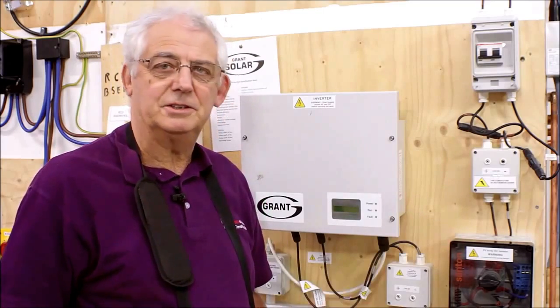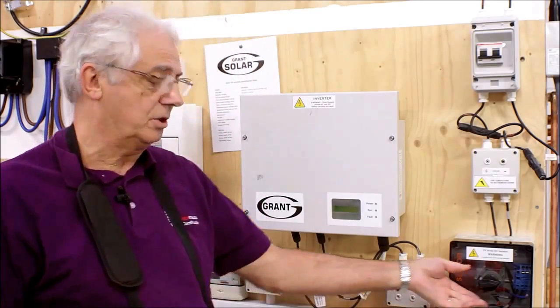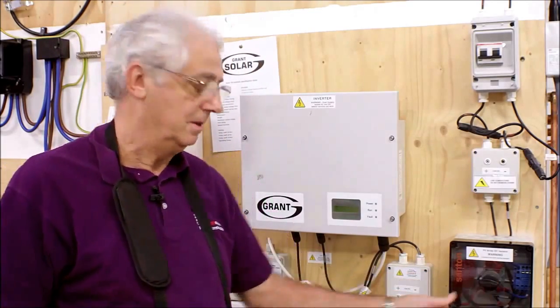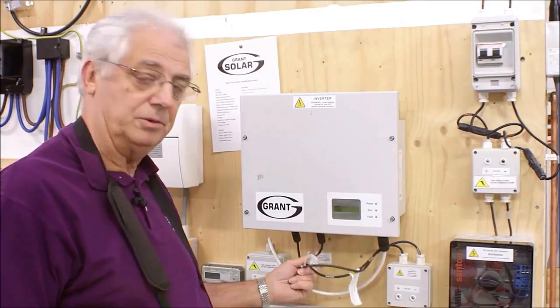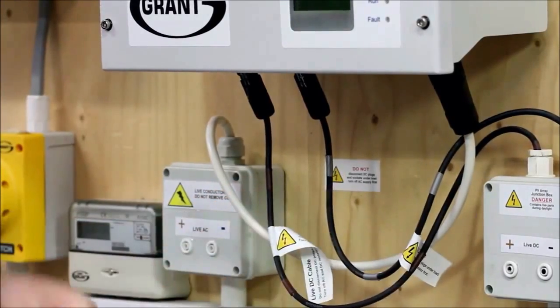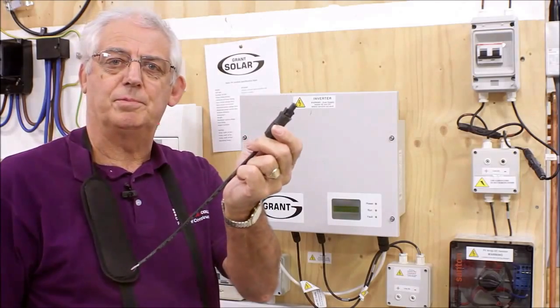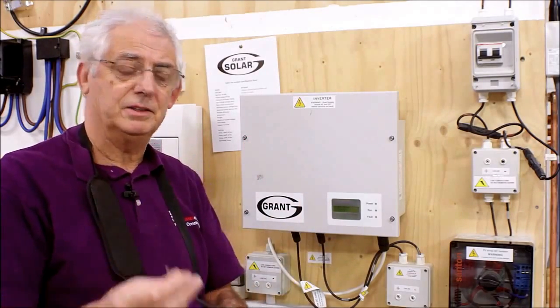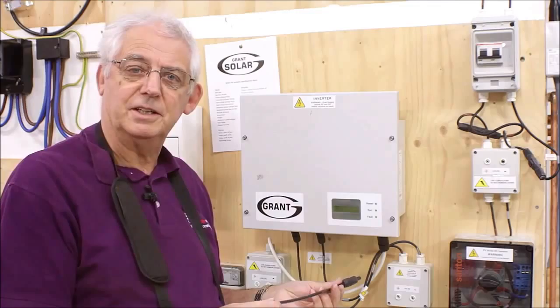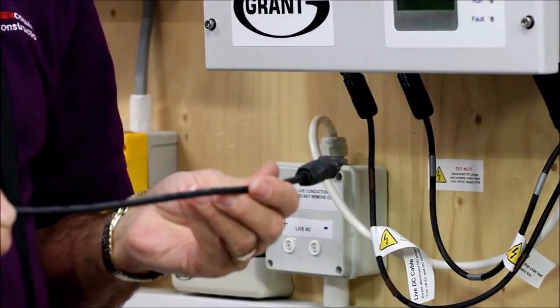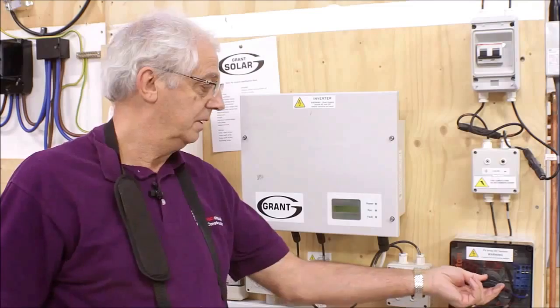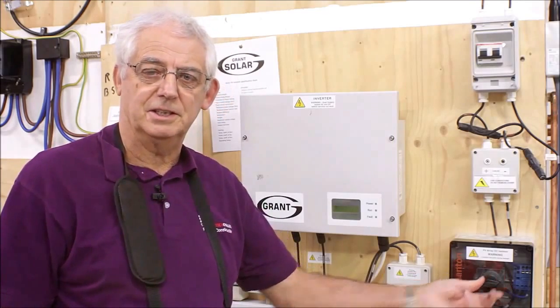Of course, we've made life easier for ourselves to carry out these tests by inserting these test points, but under site conditions, that wouldn't be available. So all you would do is you would turn off the main isolator, disconnect the two DC cables from the inverter, and you would have a male and a female plug and socket with bare ends. You join them into the disconnected leads, twist the ends together, connect your instrument, and then turn on the isolator and carry out your readings that way.